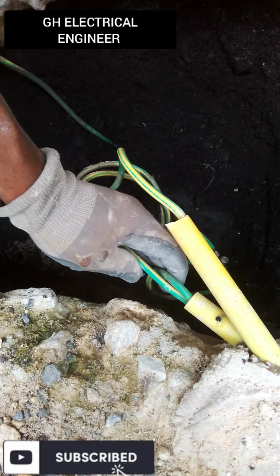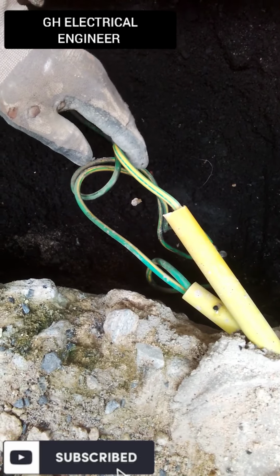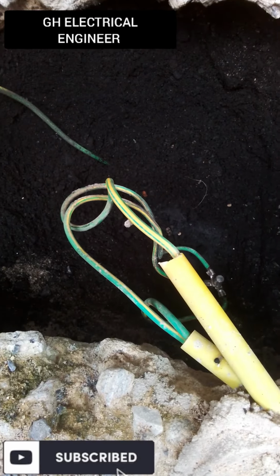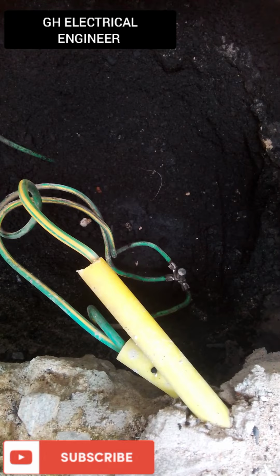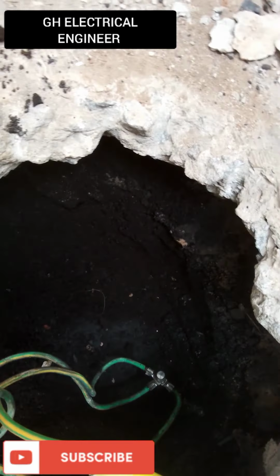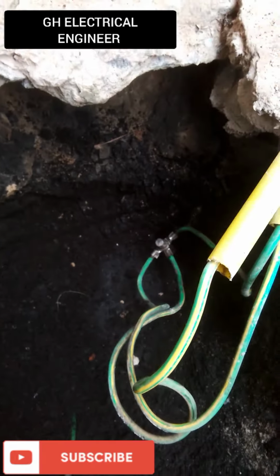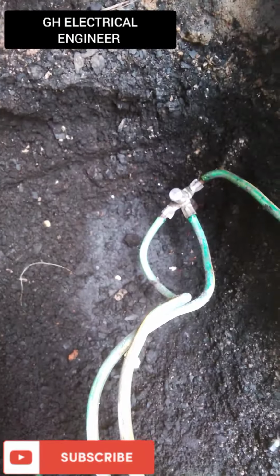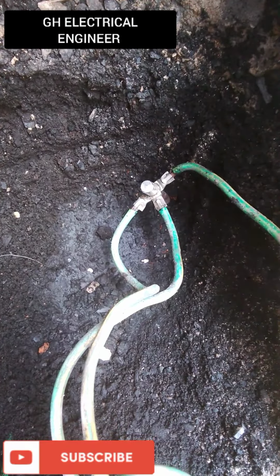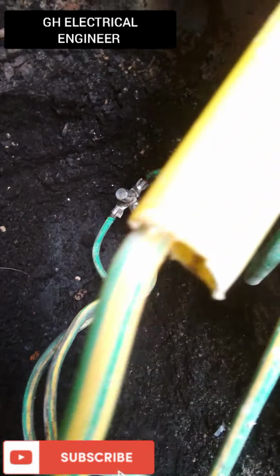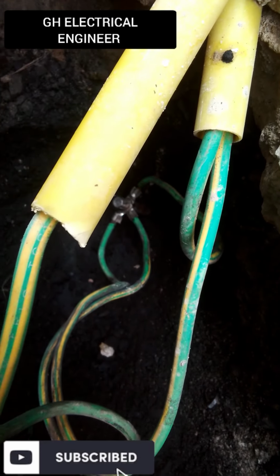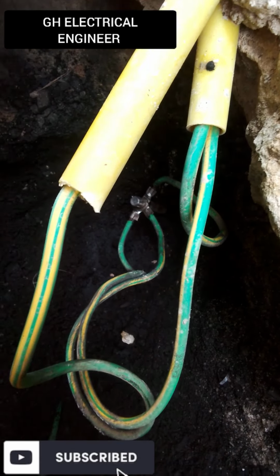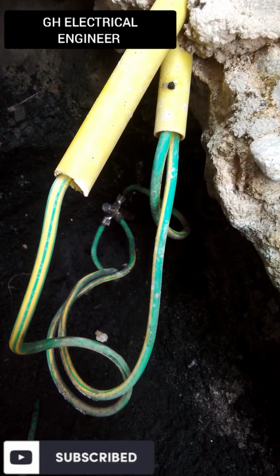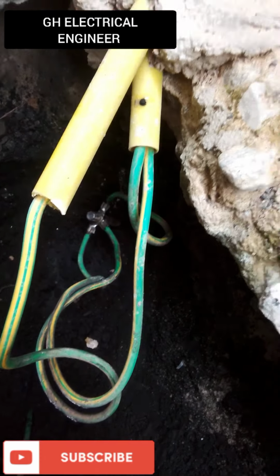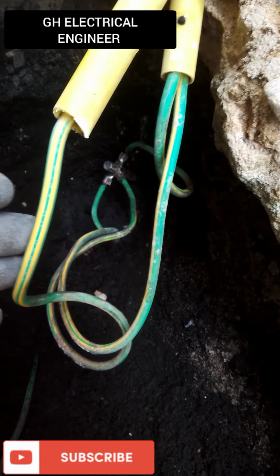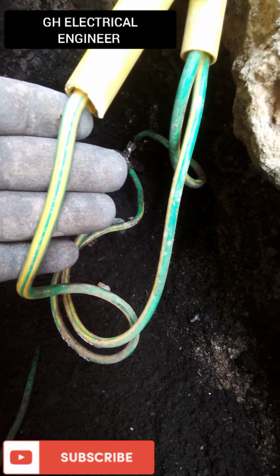The reason is simple. When we did the one earthing, we found out that we had a high resistance, a high ohms. So what we have to do, as an engineering practical mind, there are a couple of things that we should do. We should extend another rod, 5 meters away or 10 meters away.